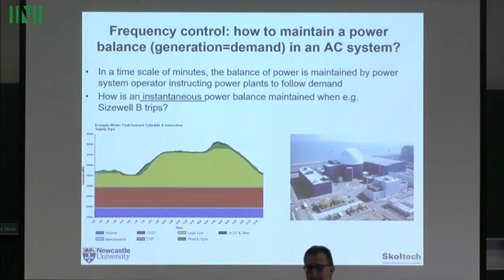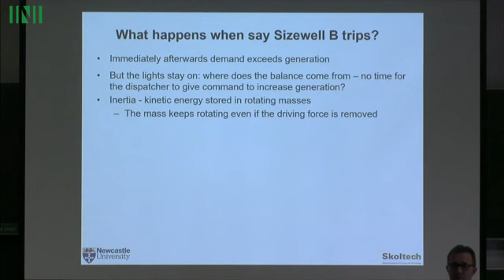Of course you do, because we are talking about frequency control all the time. When a generator is lost, the missing energy is covered by the inertia of all the rotating masses. All those generators and the remaining generation will keep rotating, and the missing energy will come from the kinetic energy, which means they will slow down. That kinetic energy provides a cushion for any imbalance between generation and demand in both directions. If there is deficit of generation, frequency drops. If there is surplus, frequency goes up.